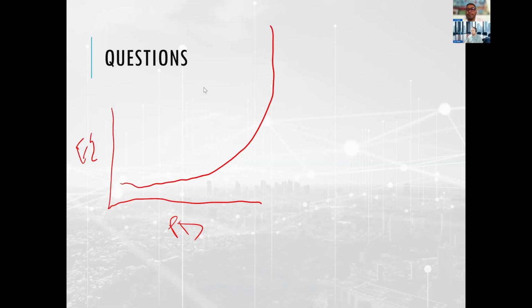As time goes on, that is the curve for pressure drop. As time goes, the pressure drop will almost exponentially shoot up, and as it shoots up, the cost of using that filter skyrockets. We don't want to change the filter here, we want to change it somewhere around here, before we reach that point where costs rise exponentially.